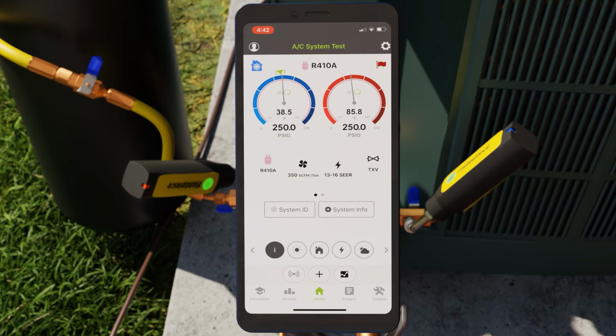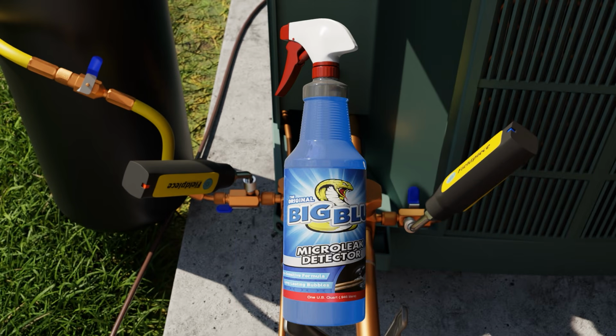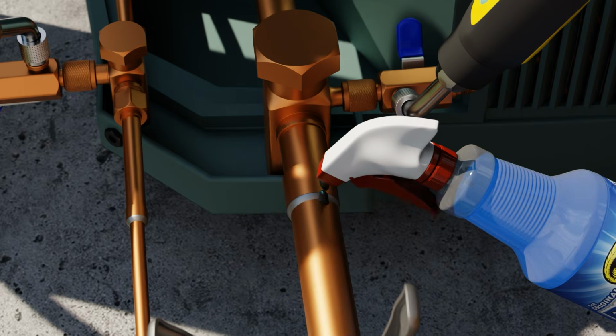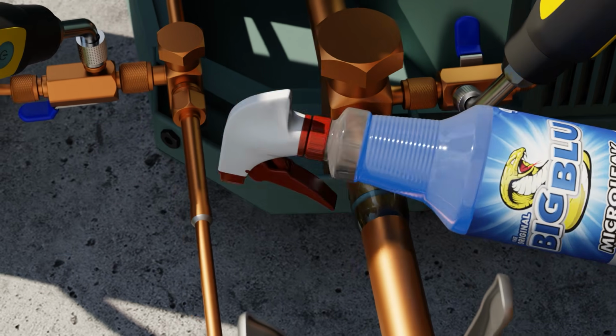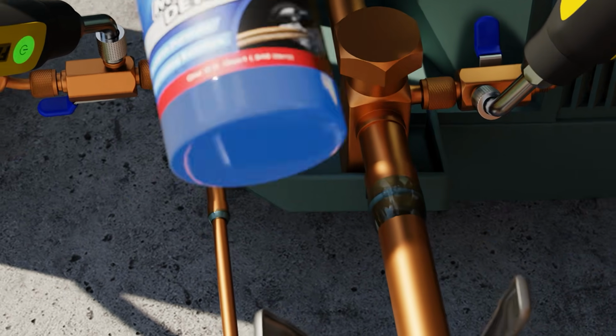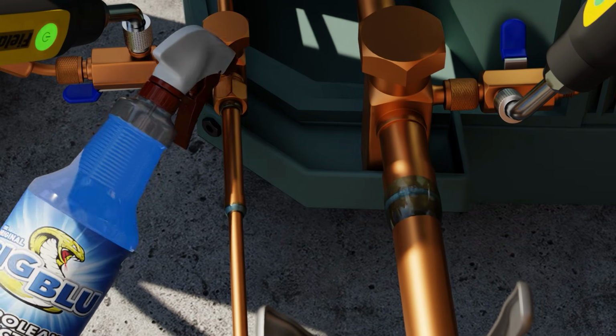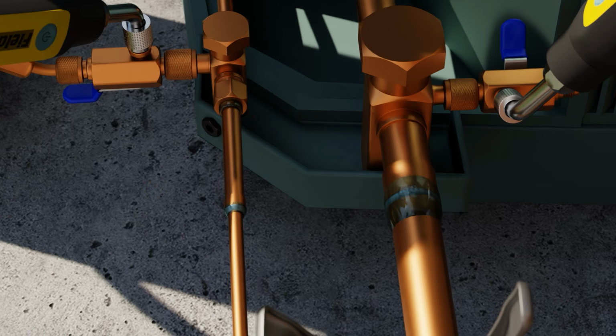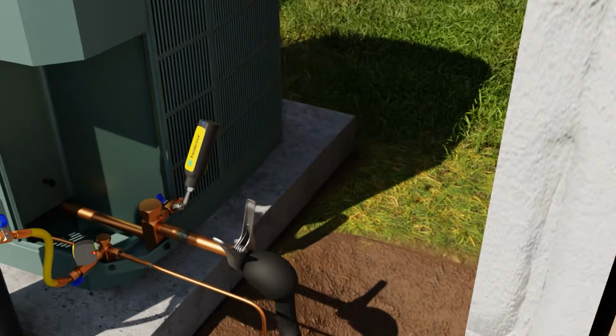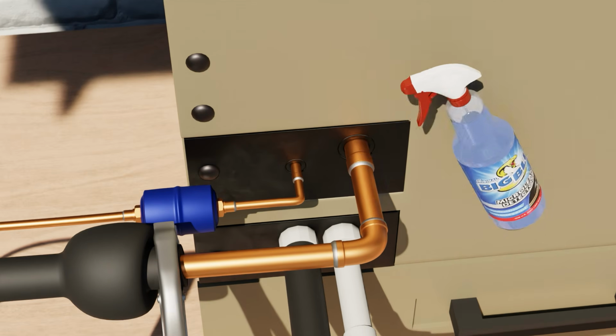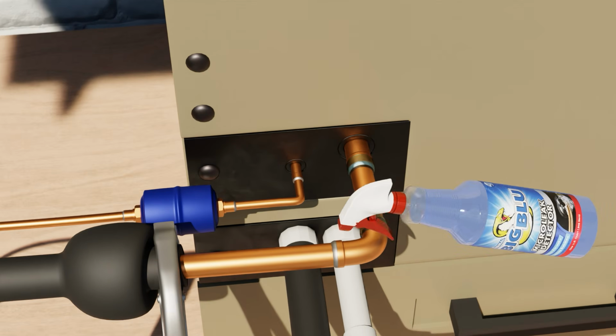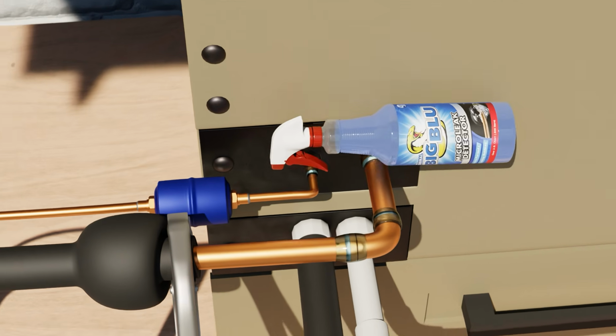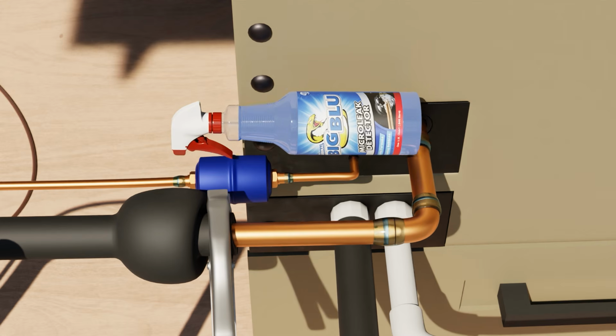A good rule of thumb is to look at the lowest pressure rating on both the evaporator coil and on the condenser and use that as your pressurization pressure. Once we get it under pressure, we're going to test each connection with a leak reactant. Some people call them soap bubbles, but this is a specially designed leak reactant to show even the tiniest leaks. When you are pressurizing the system, make sure you set it up to an exact number so that you can see even tiny changes in your pressure. Your best bet is to use a digital manifold or digital probes and to monitor the changes very carefully.